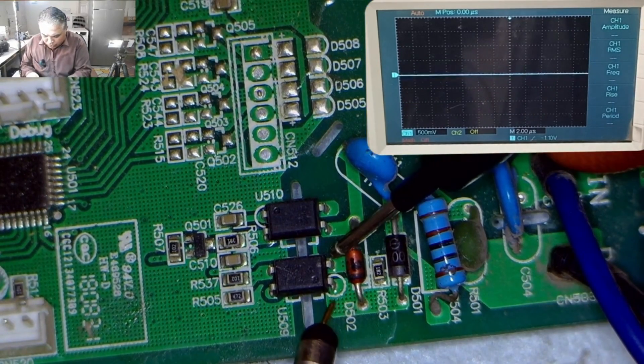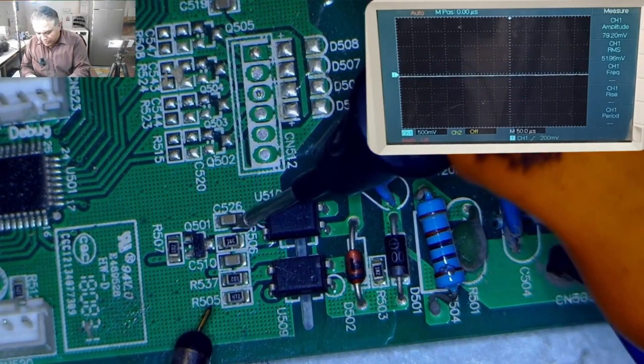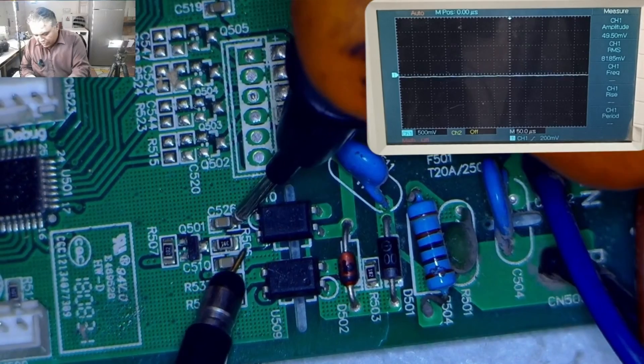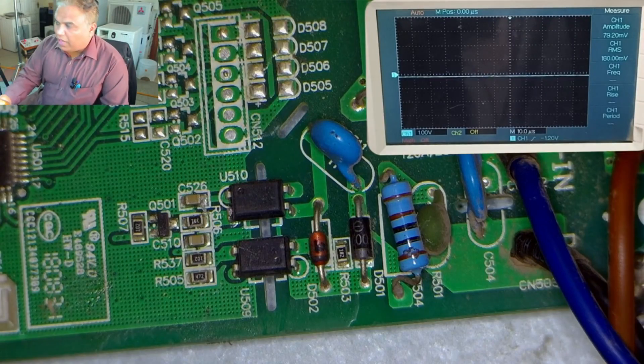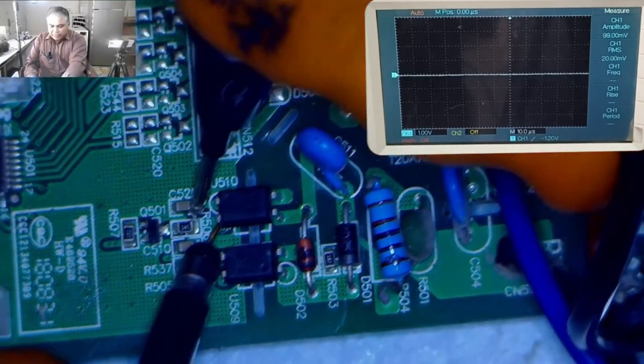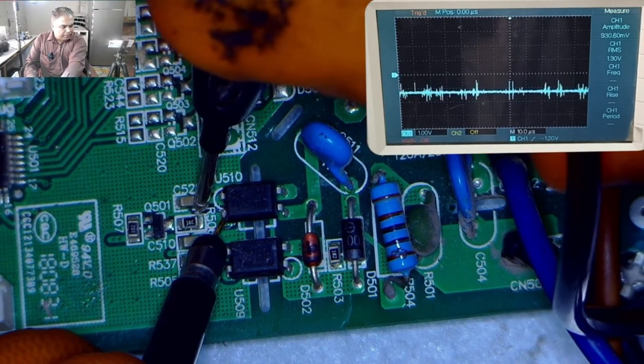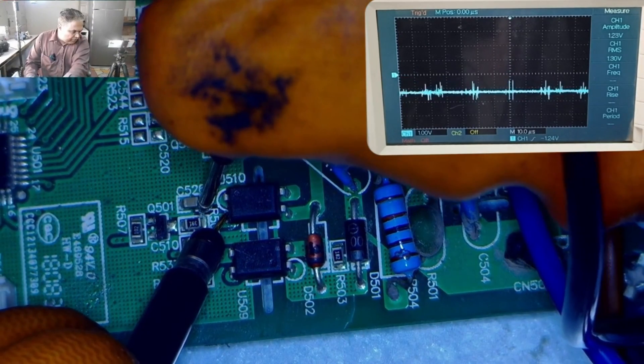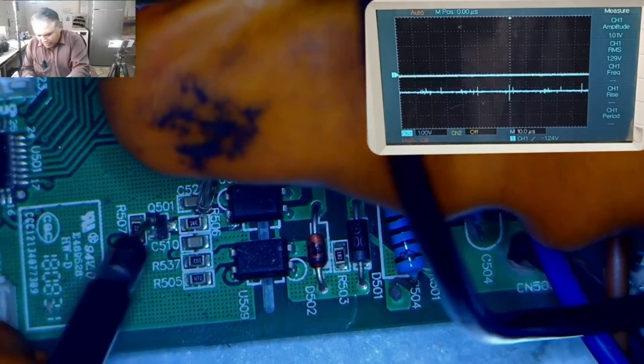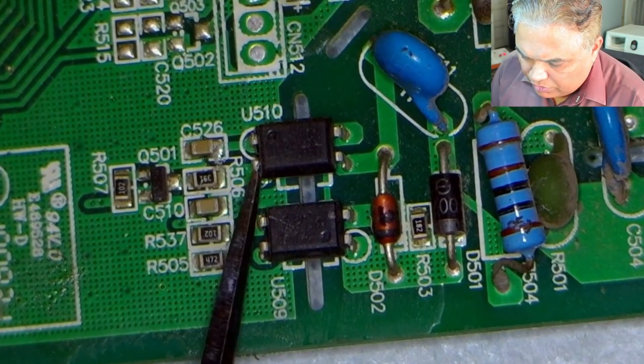I will now check the signals on this optocoupler. No signals on these pins either. I will check the signals on the other side of the optocoupler, as it is impossible that the signals are not passing from both circuit board optocouplers. To be more efficient, I will attach the probes before powering on. The circuit board has turned on — 1.2 volts are passing, but signals are not detected by the DSO. I will now clean these pins because the signal data is not being captured.